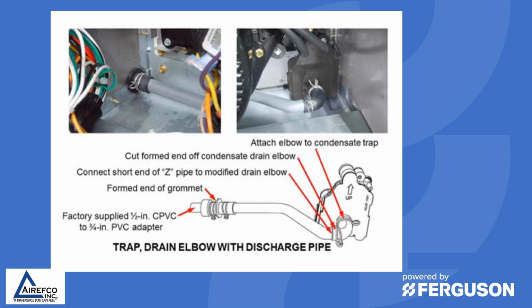We have stated in various videos before that there are kits that are available from major manufacturers to take the condensate out of the vent pipe before it gets into the furnace. Make sure that the kit that you're using to do that is certified and approved by the major manufacturer of the furnace that you're installing. If not, there could be some real liability issues with carbon monoxide poisoning possibilities. So always consult the installation guide for the furnace that you're installing, and make sure that you install the vent and the condensate trap according to the manufacturer's specifications.